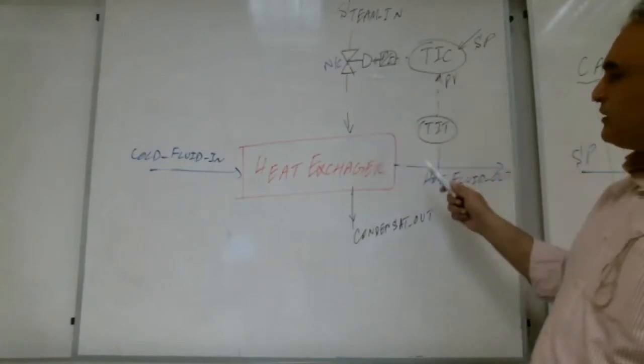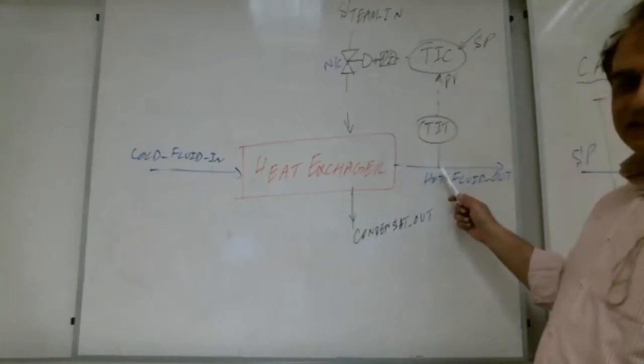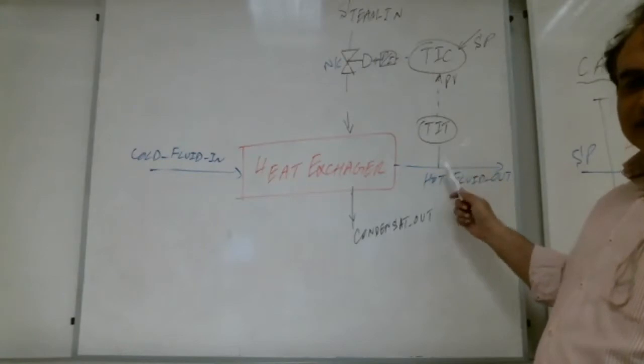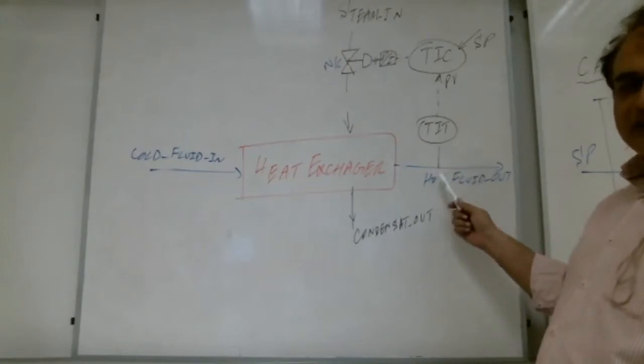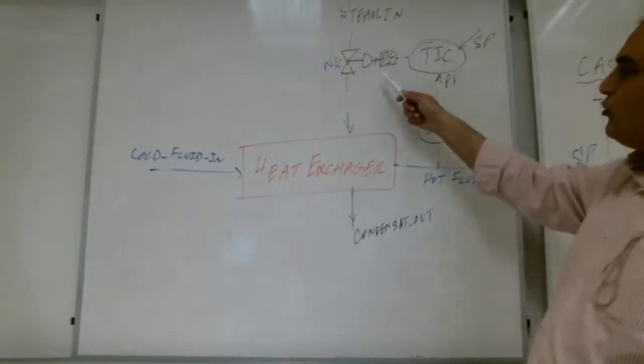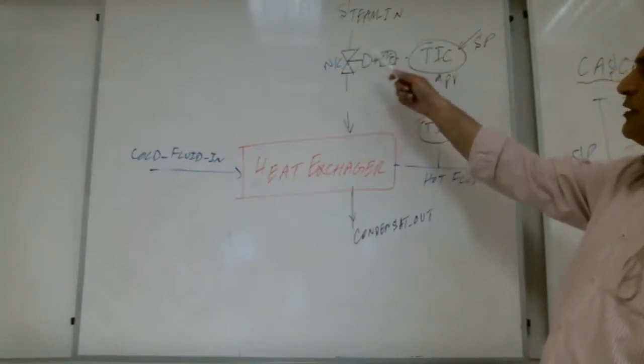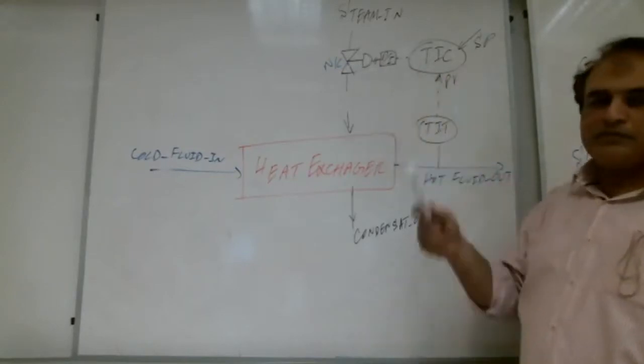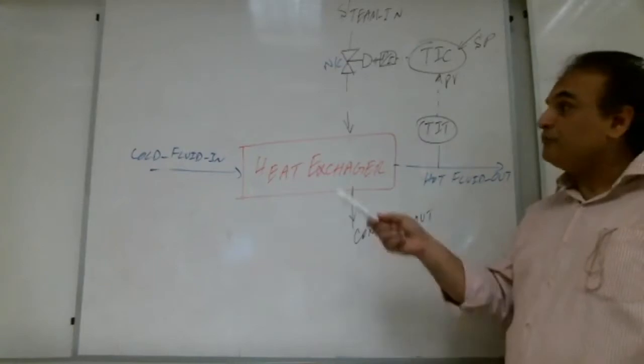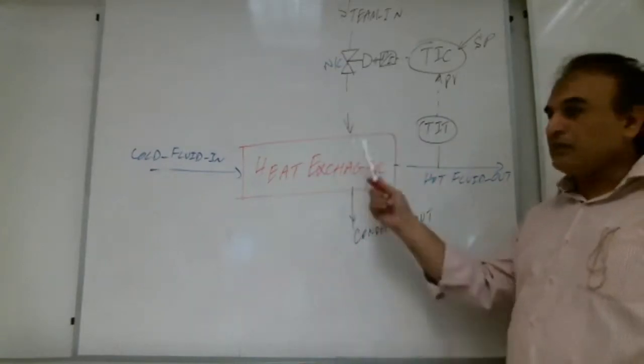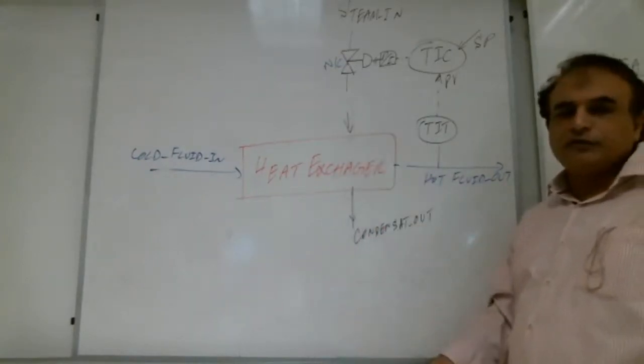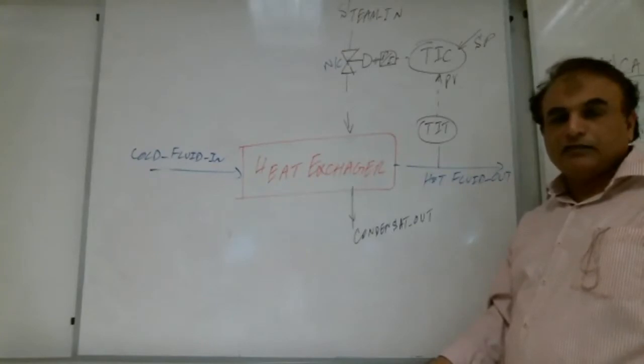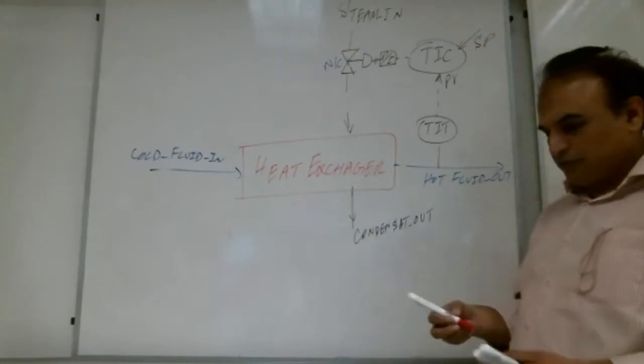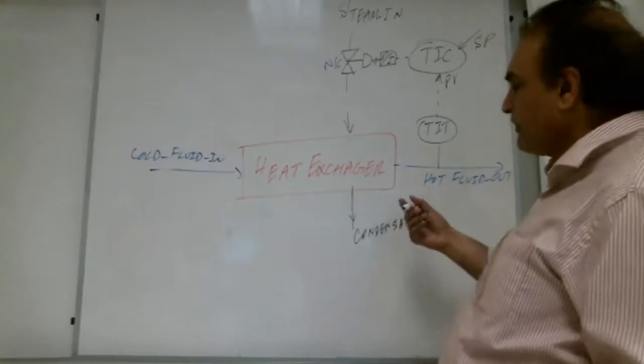If the steam is not coming, the temperature will not be attained here. The temperature will start decreasing. So the controller will think, open the valve more. The controller will open the valve more, even 100% open. But even then, no use, because the pipe is broken. So there is no use for this thing. Right, Shabab? So there is no use. So this is one problem.